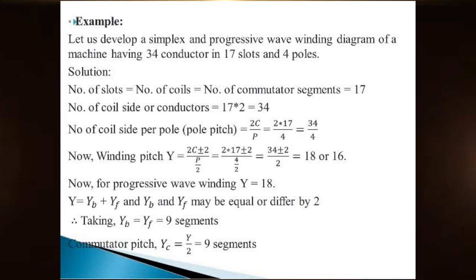Let us develop a simplex progressive wave winding having 34 conductors in 17 slots and 4 poles. That means per slot there are 2 conductors — it is a double layer winding. Solution: number of slots equals number of coils equals number of commutator segments equals 17. Number of coil sides or conductors = 17 × 2 = 34.